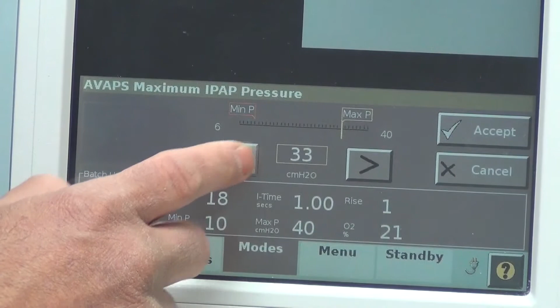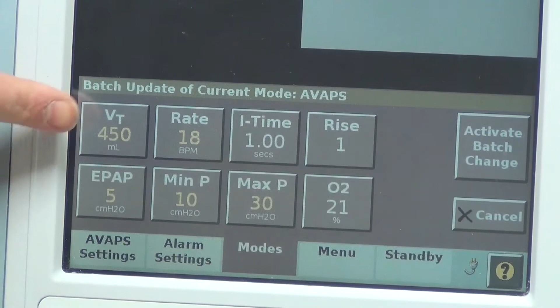Next are max and min airway pressure. These are pressures that the machine will vary between to achieve this tidal volume. A good place to start for now will probably be anywhere from 10 to 12. We'll just use 10 for now, and the max pressure may be 30. Accept. That gives us a little bit of room. If the patient's hard to ventilate, we can increase the pressures to help compensate. But these are good initial settings to start with a patient, pending the physician's decision of tidal volume, respiratory rate, FiO2 and PEEP.